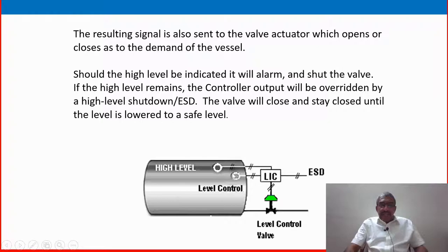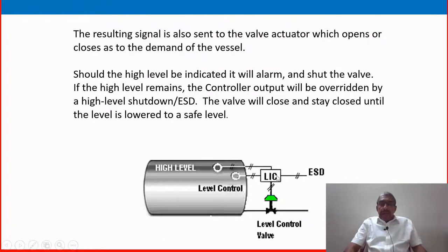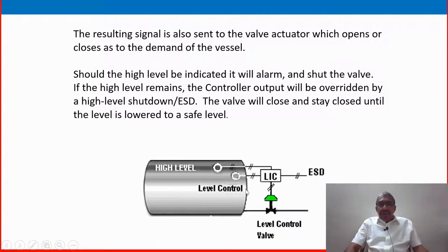The sensor measures the actual level in the tank and sends the signal to the controller through a transmitter. The LIC controller compares the level with the set point — for example, 50% — and sends the output to the control valve. Whenever the level increases or decreases, the valve adjusts accordingly. That is the normal operating condition.